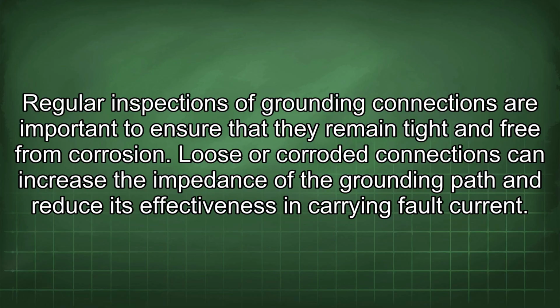Regular inspections of grounding connections are important to ensure that they remain tight and free from corrosion. Loose or corroded connections can increase the impedance of the grounding path and reduce its effectiveness in carrying fault current.